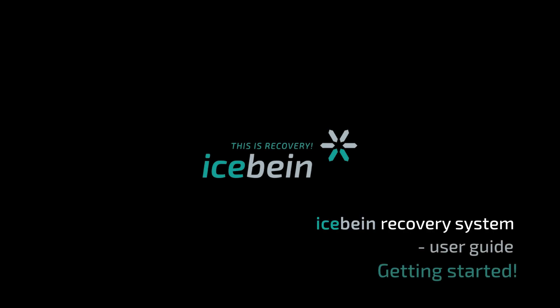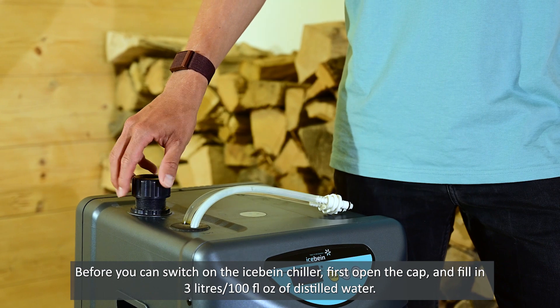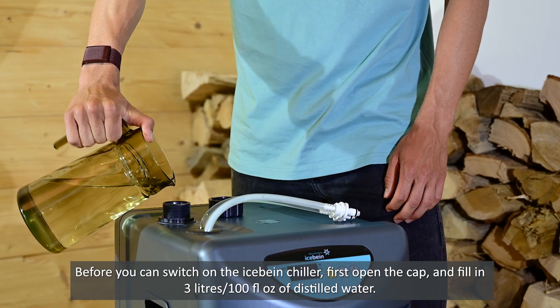icebein Recovery System User Guide, Video 1: Getting Started. Before you can switch on the icebein chiller, first open the cap and fill in 3 liters of distilled water.